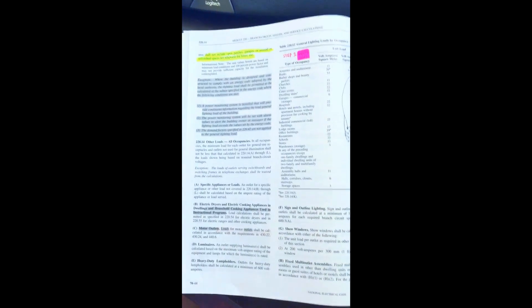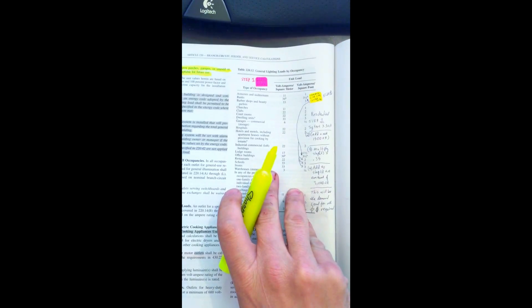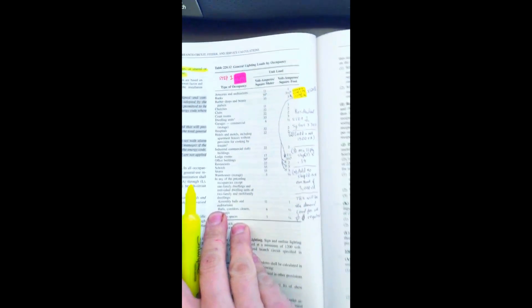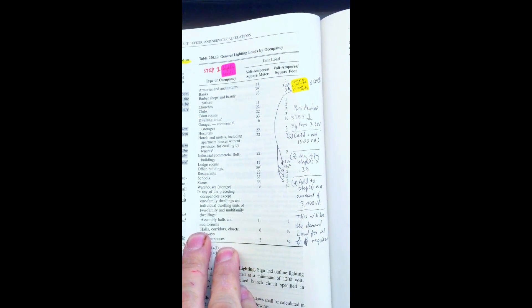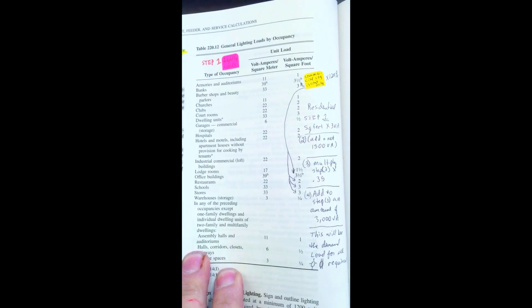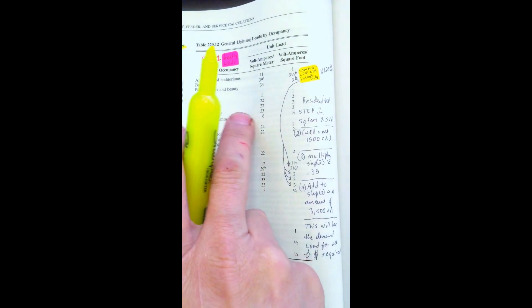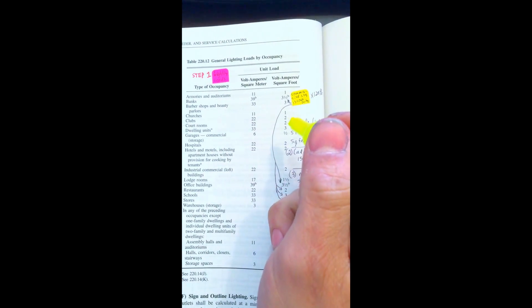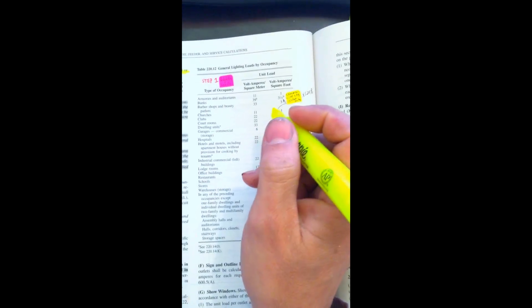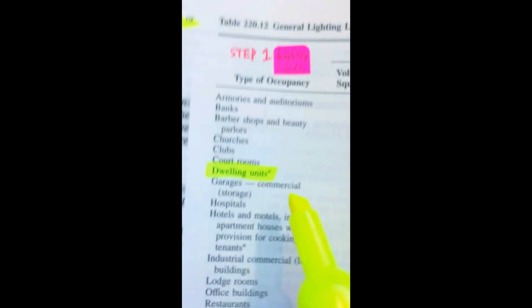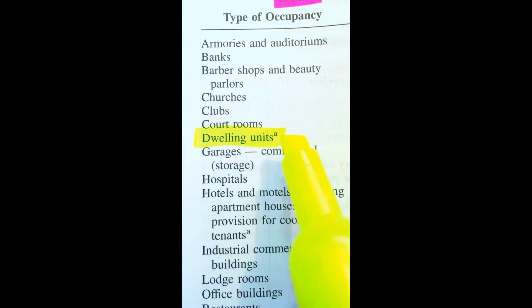Step one when we're doing service calculations, the first thing we need is to calculate the lights. If you look on page 68 under 220.12, you'll see a small table on the right hand column. You'll notice that dwelling units is listed with three volt amps per square foot. That little letter A corresponds with a note down at the bottom of the table that says see 220.14(J).